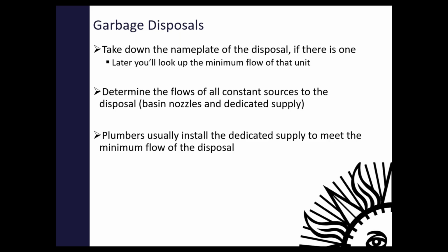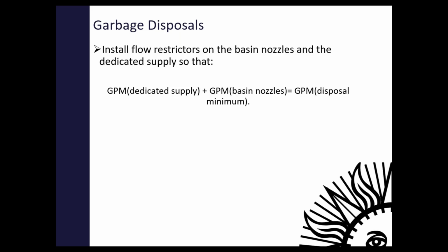So what you can do there is either install a flow restrictor on that dedicated supply, and also make sure that you have a solenoid valve on that dedicated supply. I've seen one supply where the plumber didn't install this solenoid valve, so they just had a constant flow of almost 9 GPM going through this garbage disposal, all 8760 hours. So that was a large water savings opportunity there, just from a quick inspection of a garbage disposal. So yeah, this is just telling you dedicated supply plus basin nozzles. Just make sure that's equal to the minimum of the disposal.